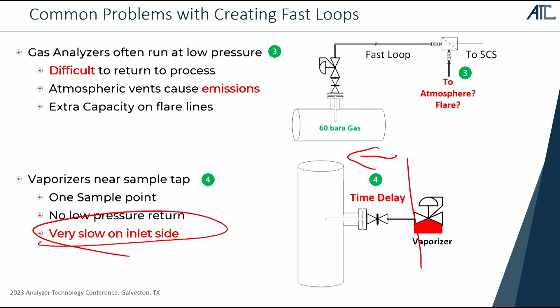Usually, if we have time delays in a liquid system that's using a vaporizer, the time delay is happening on this side of the system. And the problem is, if we're putting vaporizers out near the sample tap, we're near a process pipe where everything is one pressure. We have no low pressure return. And so these are going to run very, very slow on the inlet side. I talk about the calculations on a slide coming up. But if that vaporizer is sitting on a 2-inch pipe nozzle that doesn't have a probe in it, you'll have about an hour or an hour and a half of time delay just to try to clear the pipe nozzle. Put a probe in, you might get it down to 20 minutes. But we're going to talk about a way to do this a lot faster.